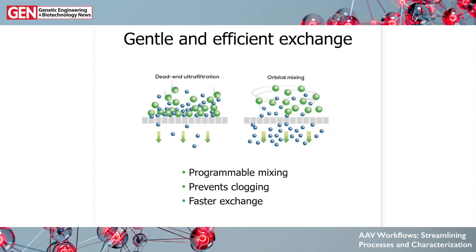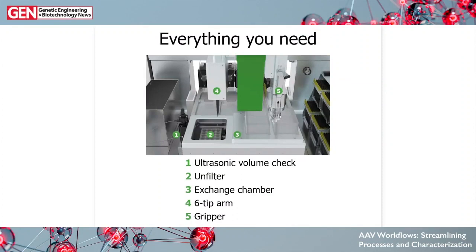The key secret sauce of BigTuna is the gentle and efficient exchange happening with positive pressure combined with orbital mixing, so things don't collect at the membrane. The AAV you want to keep in solution stays well-mixed and doesn't start aggregating as your sample concentration gets higher. BigTuna does this on an automated platform with an ultrasonic volume check, the unfilter inside an exchange chamber that closes to provide a positive pressure environment, a six-tip arm for pipetting buffers, and a gripper for moving plates.